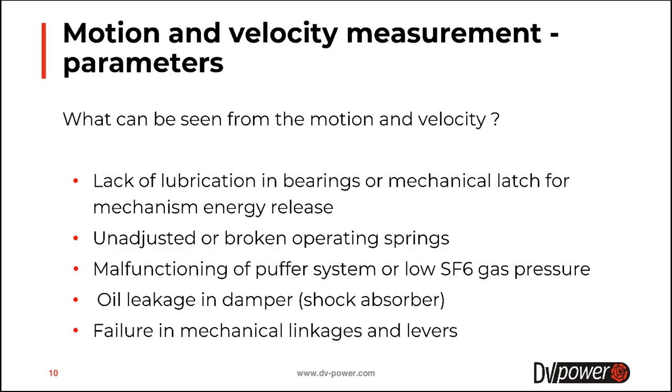Actually, they can be used to reveal lack of lubrication in bearings or mechanical latch for mechanism energy release, to reveal unadjusted or broken operating springs, malfunctioning of puffer system or low SF6 gas pressure, oil leakage in damper or shock absorber, and failure in mechanical linkages and levers.